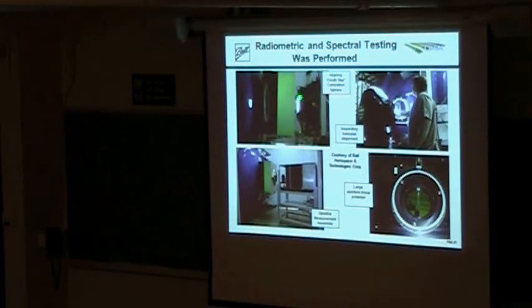So this right here is an integrating sphere. Now, an integrating sphere is basically a large sphere that's got a highly reflective material in a Lambertian sense. Inside the sphere, it's illuminated with lamps so that it presents a uniform aperture, very stable light to the instrument, and they're used for calibration on the ground. This one was actually called the Death Star sphere because it kind of looked like the Death Star, and you'll see that in a minute. One of the tests we did for calibration is to use this. It is butted up against a chamber window, an optical window in the chamber, so that the solar or the Earth viewing aperture is aimed at this integrating sphere, and then we collect a lot of data, numerous times, in numerous different conditions, temperature and so on, in order to calibrate the instrument.